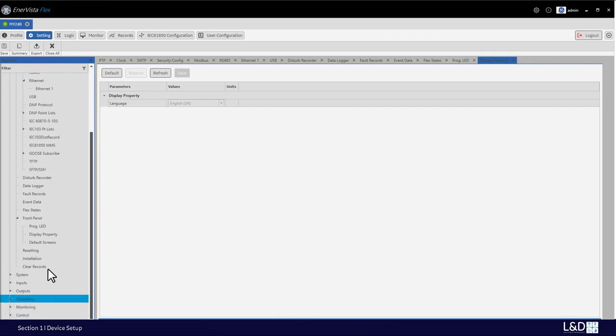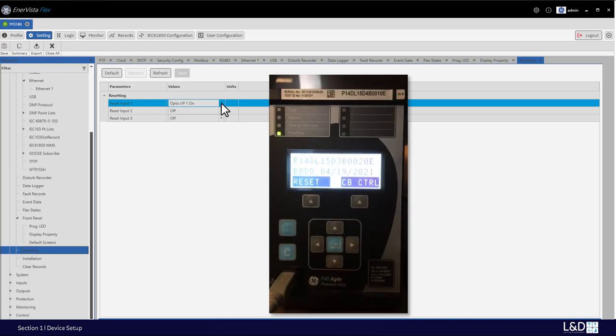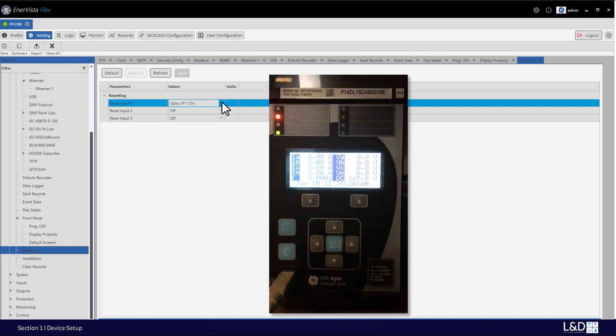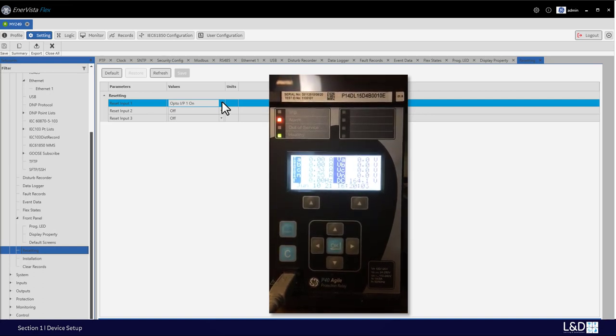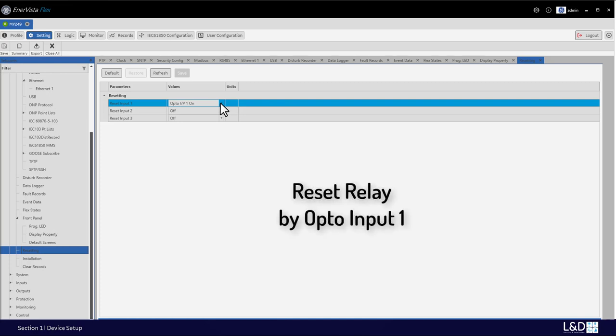For resetting, we can choose three FlexLogic operands to reset instead of pressing the C button on the front panel. We can press C if logged in as administrator, or with bypass set. Another way is to use operands — for example, an opto input — so that we don't need to log in as administrator. We can just use the opto input to reset the relay, for example to reset the trip LED.